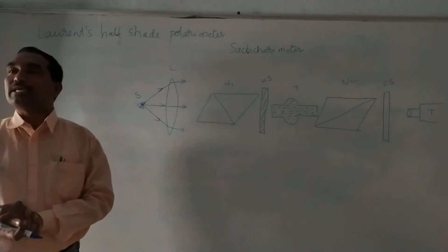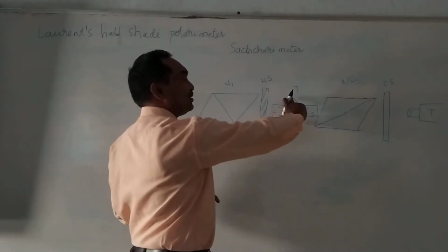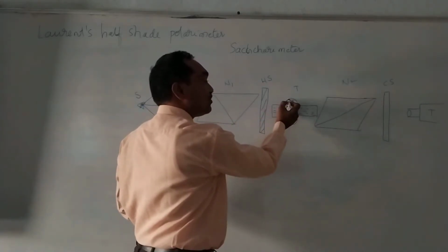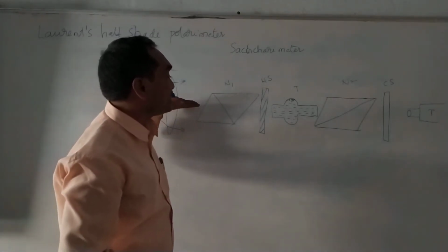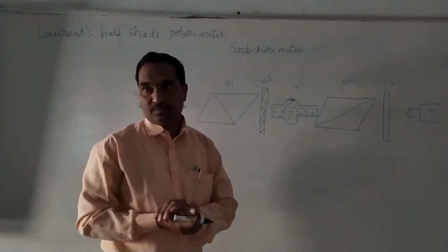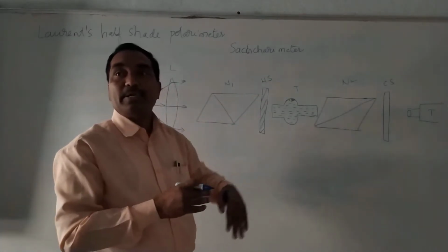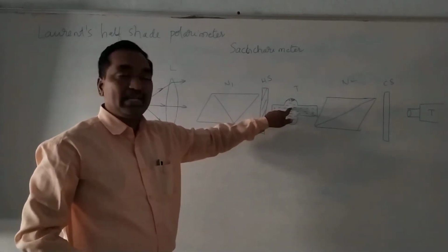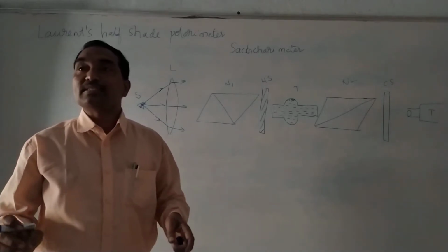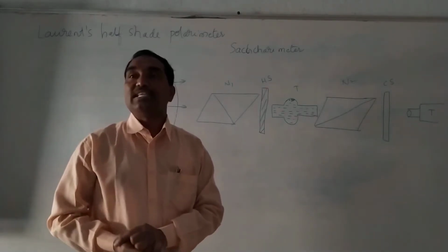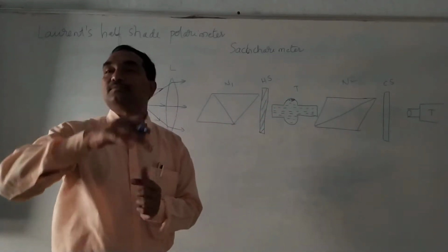So we have taken glass tube T. It is filled with the sugar solution, in which the middle of the tube has a larger diameter, because any water or liquid bubbles will move upward. Then there is no obstruction to the light passing through the liquid. If it is not so, and the middle does not have a larger diameter, these bubbles may stay at the middle. Then the light rays pass through the bubbles, and accurate reading does not arise. For this purpose, in glass tube T the central portion has a bigger diameter to eliminate this.